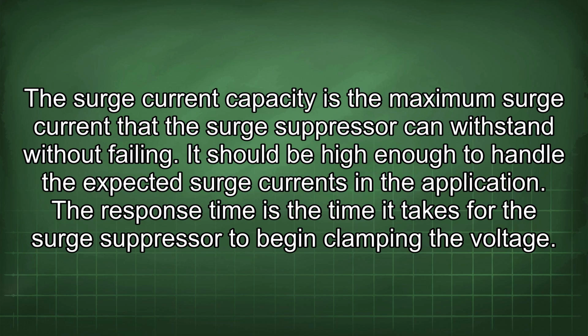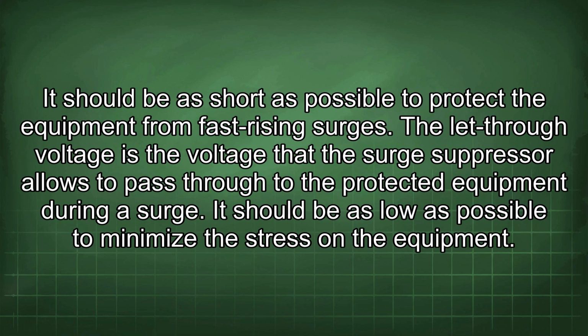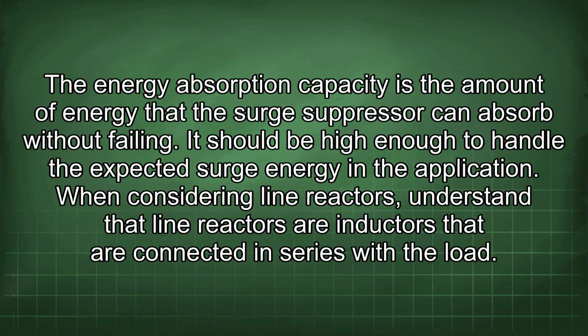The response time is the time it takes for the surge suppressor to begin clamping the voltage. It should be as short as possible to protect the equipment from fast rising surges. The let-through voltage is the voltage that the surge suppressor allows to pass through to the protected equipment during a surge. It should be as low as possible to minimize the stress on the equipment. The energy absorption capacity is the amount of energy that the surge suppressor can absorb without failing. It should be high enough to handle the expected surge energy in the application.